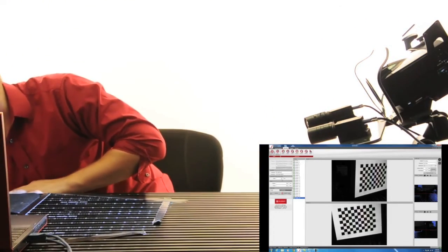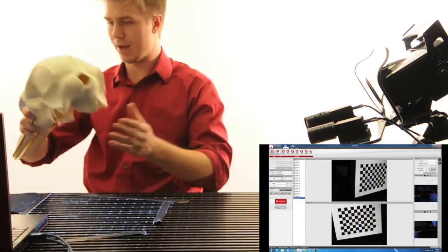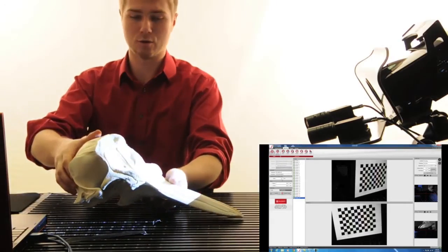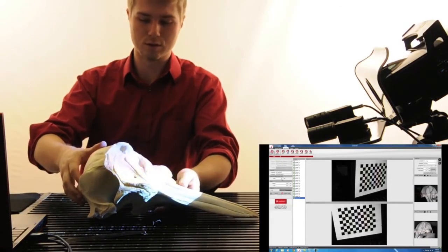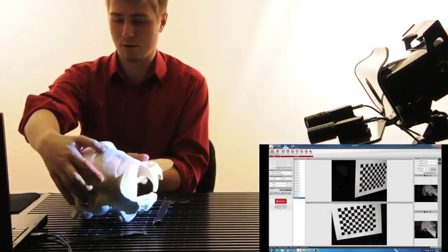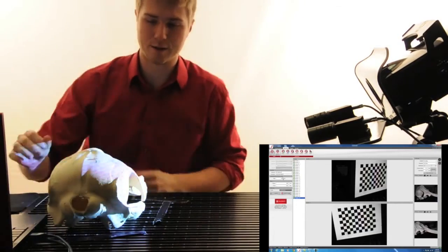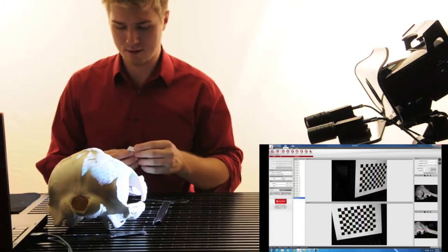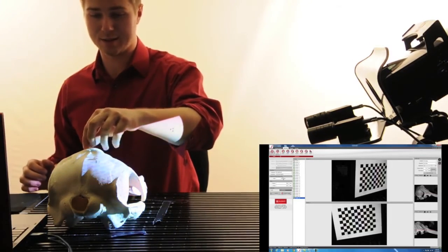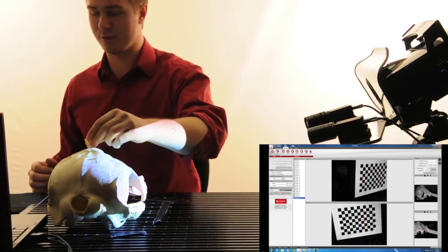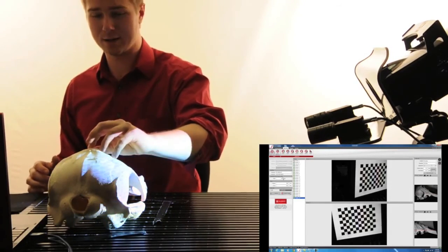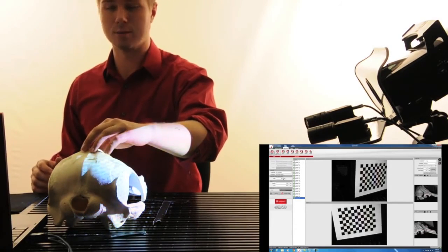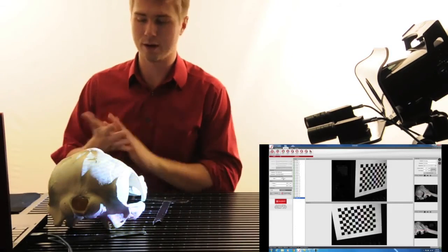That is very important to ensure that you get the proper accuracy and the correct sizing on your images. That number does define the actual size of the scan, so it is referencing back to those individual artifacts. If that number is for some reason wrong, then your data will also be wrong. So just another quick note.